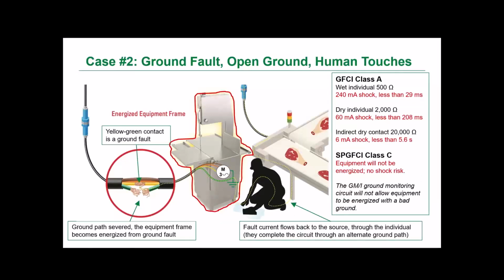In our second case, let's add a human contact here. So in the red circle, again, you can see the severed ground. And this time, the ground fault is created by contact from the yellow to green conductors. Now, when you have cable damage like that, it's not too difficult to believe that that could have occurred. The Class A GFCI could allow this machine to be energized and possibly run because there would be no ground fault path for the ground fault current.